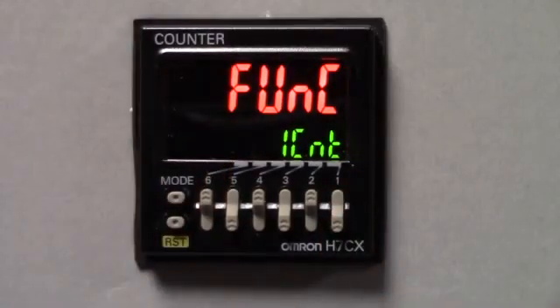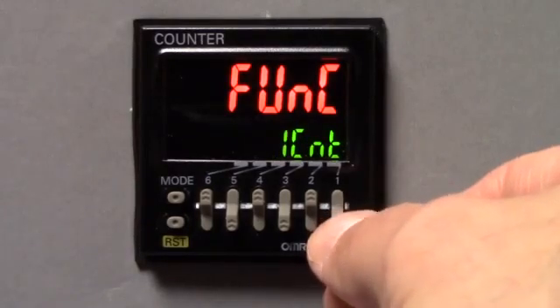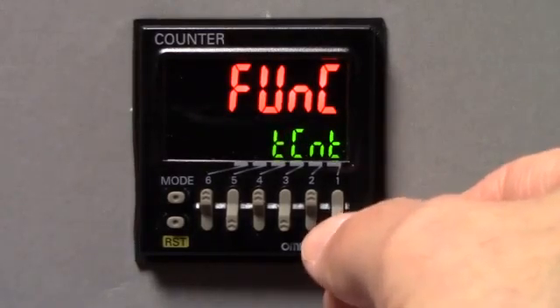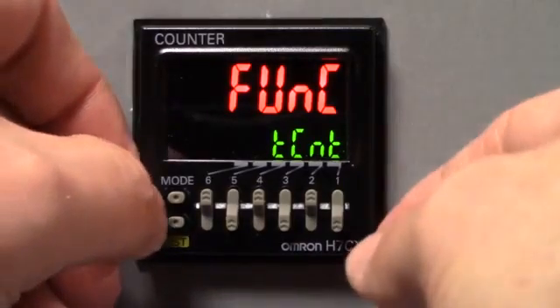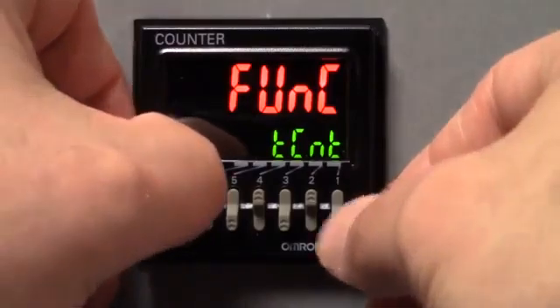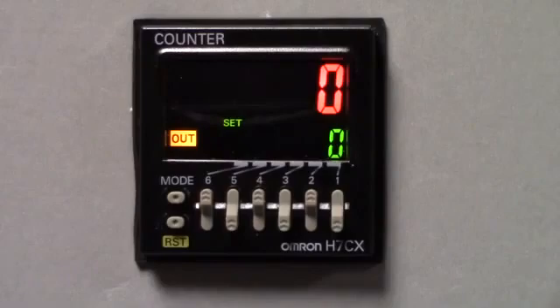So that takes us into the parameter setup. You have a one stage preset, which is the factory default, which we are not going to do. We are actually going to do a total and preset counter. So we're going to take the number one key, and we're going to toggle it until you have the TCNT. So this is the T indicates total. Once you have that set, we will now then press the mode key first, and then press the number one key. That brings us back to the initial screen.